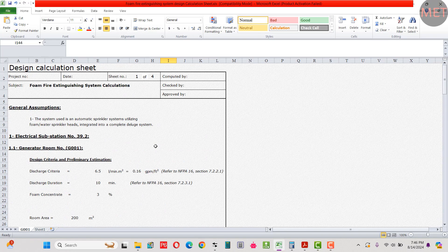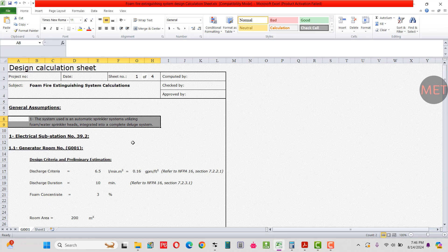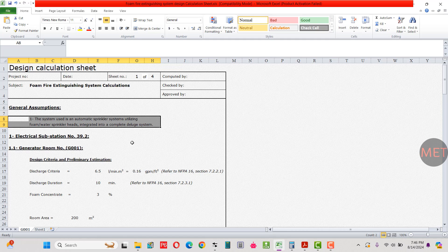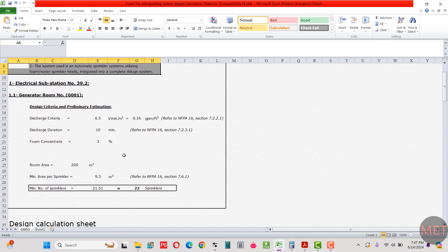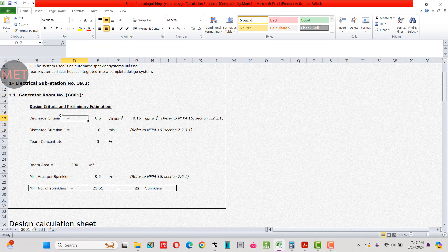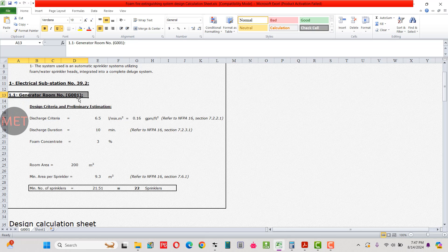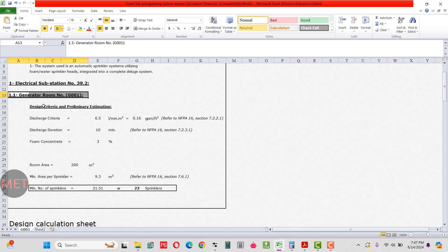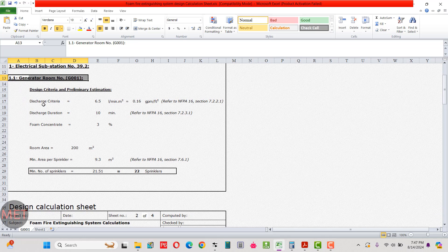The general assumption is that the system is an automated sprinkler system utilizing foam water sprinkler heads integrated into a complete deluge system. We've taken the example of an electrical substation, number 39.2, and inside we have a generator room referenced as G001. We have some inputs that need to be used as per NFPA standards to calculate the number of sprinklers and other factors.